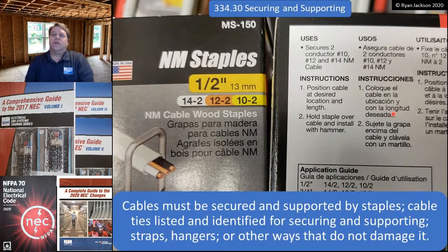334.30, securing and supporting. Cables must be secured and supported by staples or by cable ties that are listed and identified for securing and supporting. We'll talk about that next. Or straps or hangers or other ways that don't damage it. Just secure it and support it however you want, just don't damage the cable. That's pretty much the rule here.